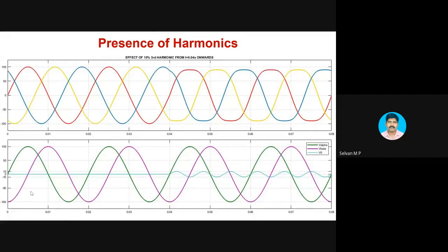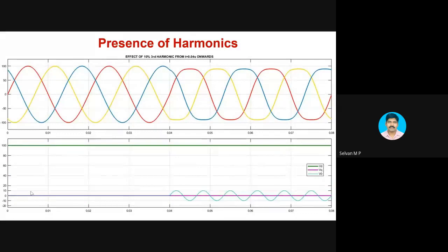And of course, this DQ transformation helps even with harmonic components. If I have a third harmonic component in this current, then the third harmonic component will get replicated in this. When you do a DQ transformation, there will be a third component called V0, the zero sequence component. You can see here, this is the D component and the purple is the Q component, and we have a third harmonic. So the third harmonic is reflected in the zero sequence component.